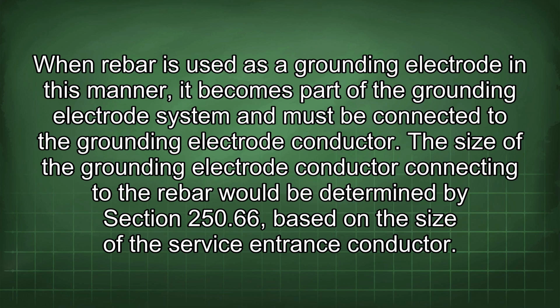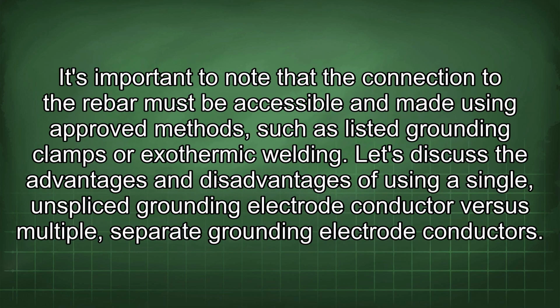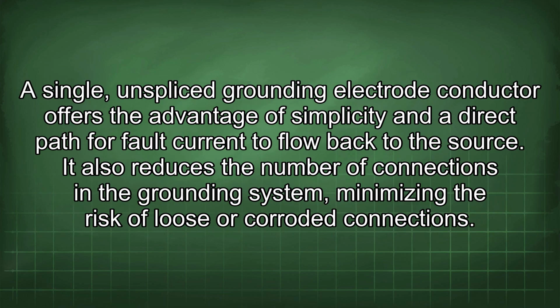The size of the grounding electrode conductor connecting to the rebar would be determined by Section 250.66 based on the size of the service entrance conductor. It's important to note that the connection to the rebar must be accessible and made using approved methods such as listed grounding clamps or exothermic welding. Let's discuss the advantages and disadvantages of using a single, unspliced grounding electrode conductor versus multiple, separate grounding electrode conductors. A single, unspliced grounding electrode conductor offers the advantage of simplicity and a direct path for fault current to flow back to the source. It also reduces the number of connections in the grounding system, minimizing the risk of loose or corroded connections.